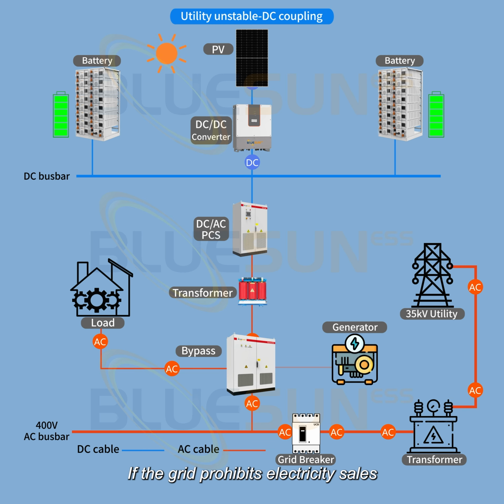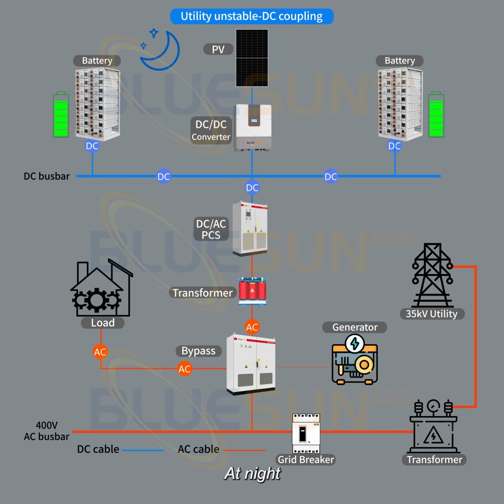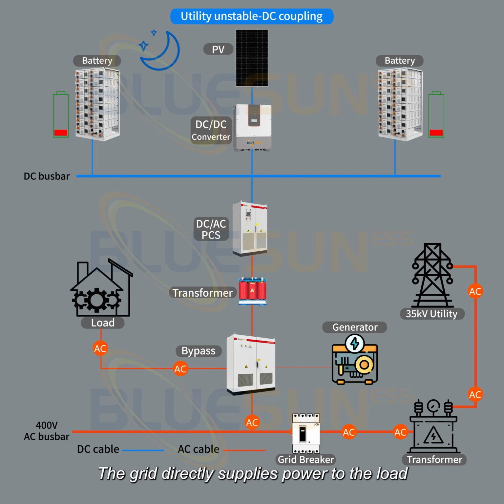If the grid prohibits electricity sales, the PV power is used solely for load consumption. At night, the battery system supplies power to the load. When the battery is nearly discharged, the PCS controls the battery system to stop discharging. The grid directly supplies power to the load through the bypass, and the load is unaware of the power outage.